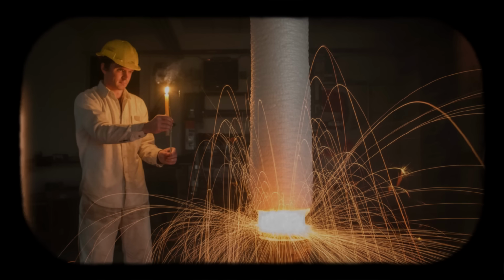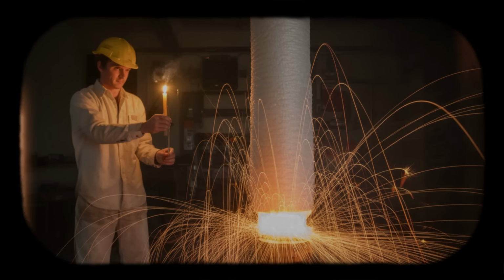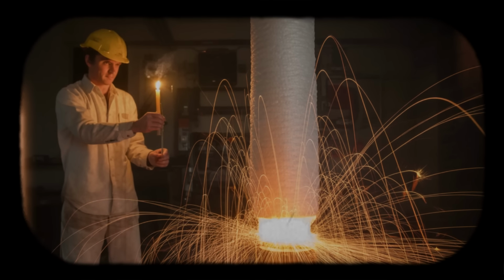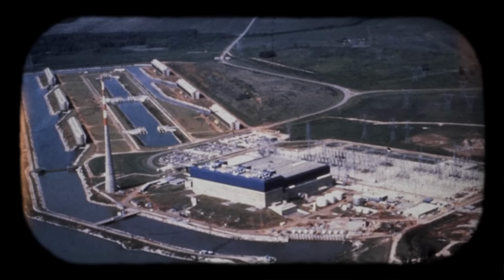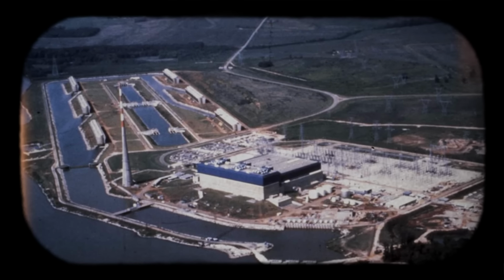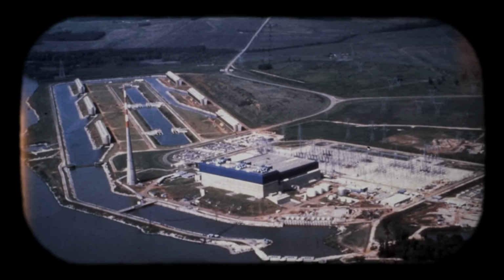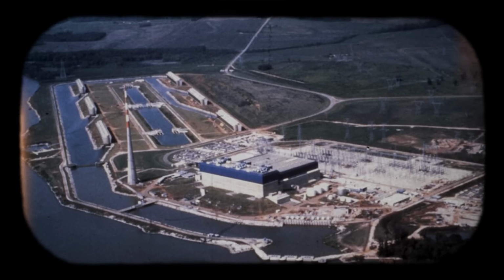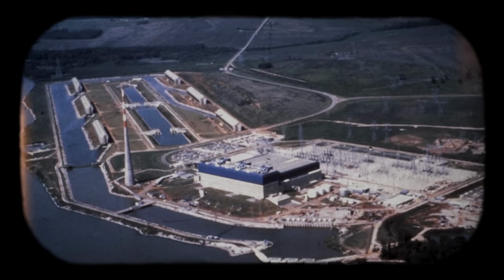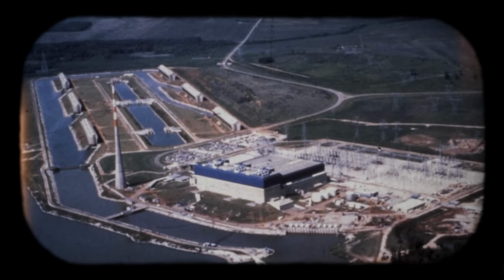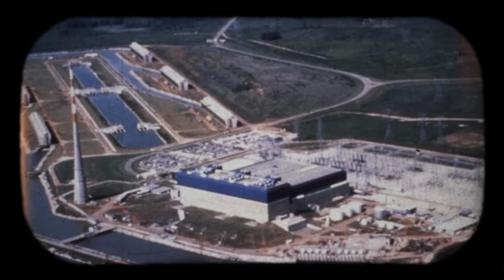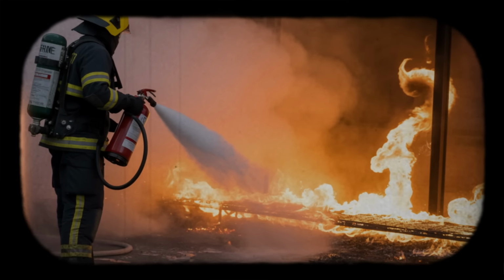This is the efficiency of shared cable trays. One routing path serves multiple purposes. Under normal conditions, it works perfectly. Under fire conditions, it creates cascading failures. The operators do not have fire alarms or smoke detection in the cable spreading room. The room is not considered a high-risk area. It contains no rotating equipment, no high-temperature processes, no flammable liquids. It is simply a routing space. Fire suppression systems in the room are minimal. The connection between the flickering control panel and a growing fire in the cable spreading room remains unknown.